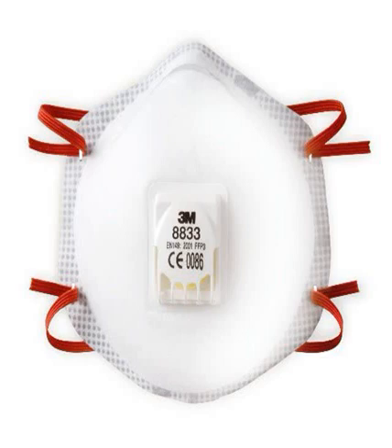EN 149 requires an additional paraffin oil aerosol test and it tests at a range of different flow rates and defines several associated permissible pressure drop levels. The EN 149 standard defines performance requirements for three classes of particle filtering half masks: FFP1, FFP2 and FFP3.